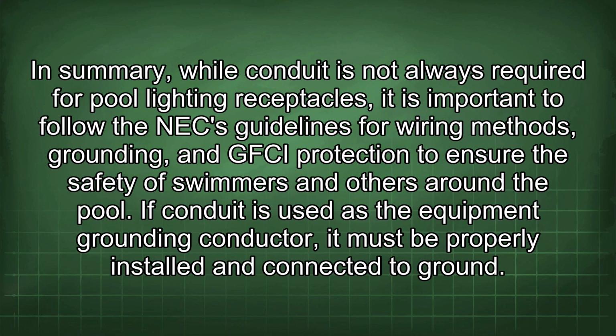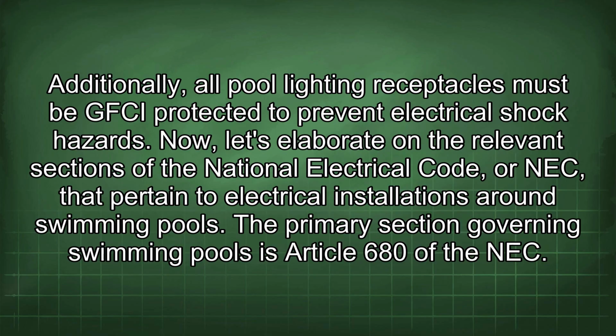In summary, while conduit is not always required for pool lighting receptacles, it is important to follow the NEC guidelines for wiring methods, grounding, and GFCI protection to ensure the safety of swimmers and others around the pool. If conduit is used as the equipment grounding conductor, it must be properly installed and connected to ground. Additionally, all pool lighting receptacles must be GFCI protected to prevent electrical shock hazards.